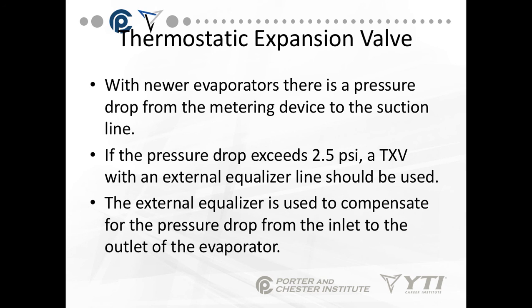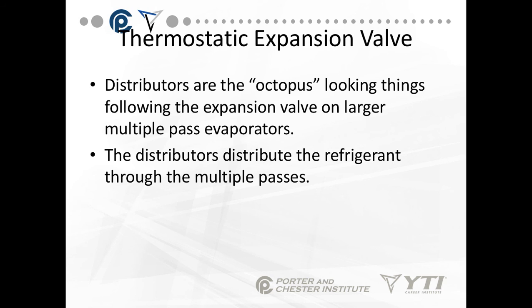With newer evaporators, there's a pressure drop from the metering device to the suction line. If the pressure drop exceeds 2.5 PSI, a TXV with an external equalizer line should be used. The external equalizer is connected to the suction line after the bulb, and it's used to compensate for the pressure drop from the inlet to the outlet of the evaporator. We also have distributors on some newer and heavier coils — octopus-looking things that follow the expansion valve on large multi-pass evaporators, more often seen in air conditioning. Distributors distribute the refrigerant through the multiple passes of the evaporator.